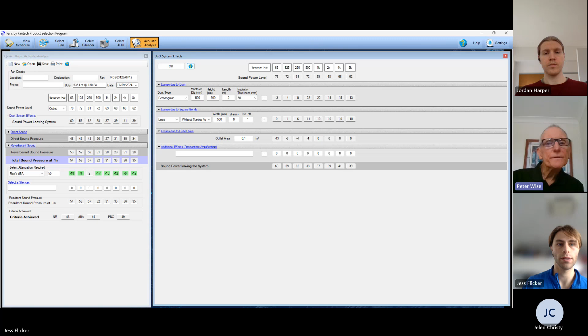But you wouldn't do a proper hardcore acoustic analysis with this - it's more just to get an idea when you've got a fan somewhere, and a room that's maybe very live or not so live, so you can see roughly what the sound will be doing through that system. It gives you a level of comfort that your design will be okay, because you won't know until the systems are commissioned, and if there's a noise problem then, you think, what do we do now? So if you think about it during design and make provision to attenuate the noise if needed, you shouldn't have any worries at the end.